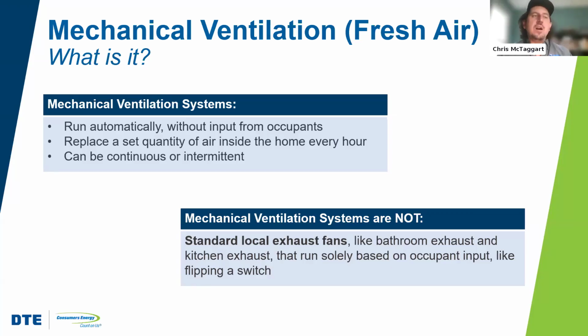And so, oftentimes in Michigan, we see a fresh air duct coming into the return side of a plenum of a heating and cooling system. It just basically relies on whenever that heating and cooling system runs, then we're getting fresh air in the house. Well, the problem with that is that, take today, we have a very moderate day here in Michigan, temperature wise. I'm neither heating nor cooling my house, and so my air handler is not running. So I don't have any mechanical ventilation going on right now, and that's probably leading to me having more stagnant air inside my home. So the idea behind the mechanical ventilation requirements for Energy Star is that it's either continuous or it's intermittent, but it's on some type of program schedule.